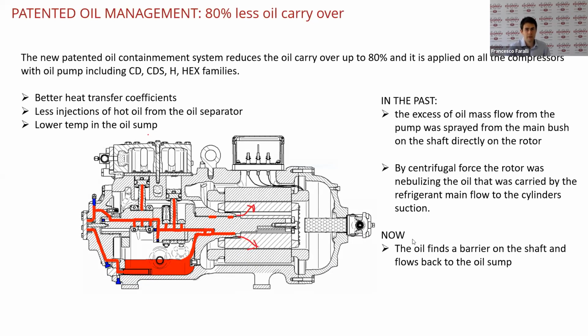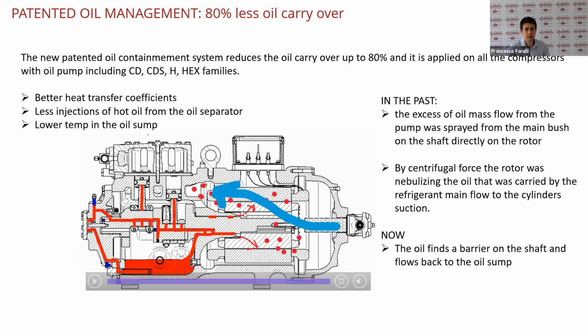So what happened with the previous design was that some oil was flowing from the bushes in these directions. And when the oil was flowing here, some droplets were nebulized by the rotor. And here the blue arrow shows you the suction flow. So what happened in the past is that we had some suction flow that was trapping some oil droplets, and these oil droplets were then transported to the cylinder and then leaving the compressor.